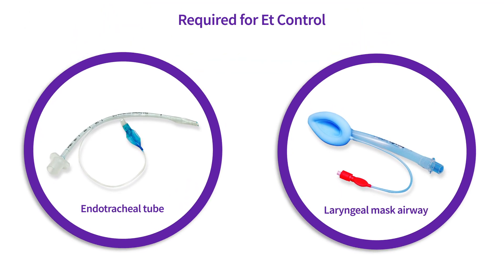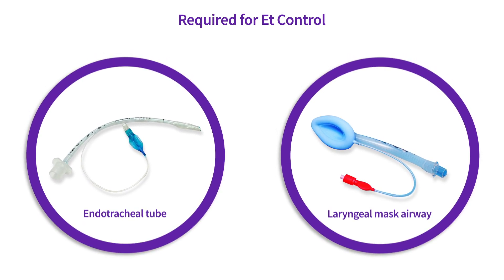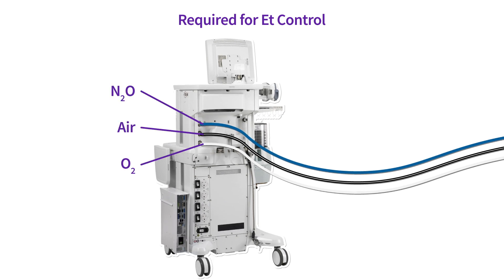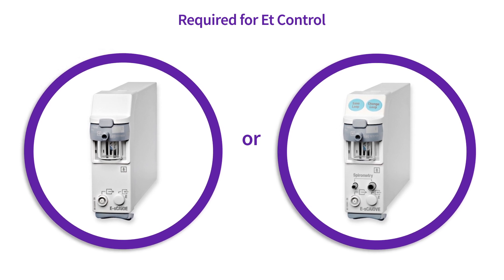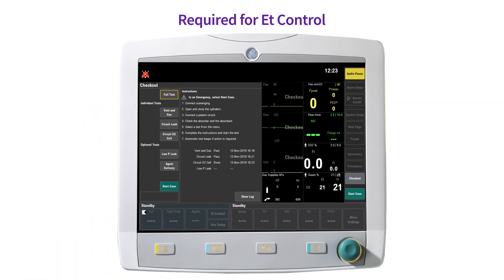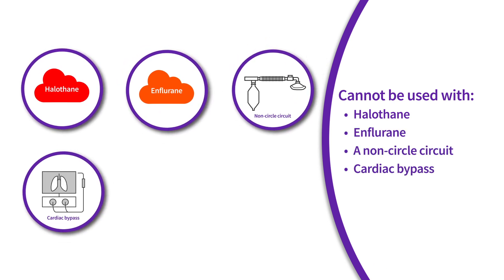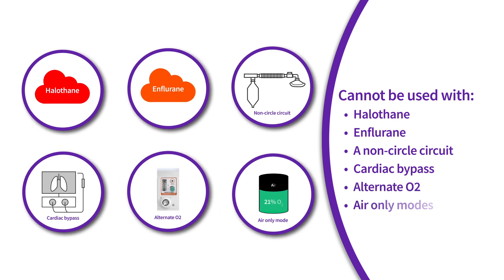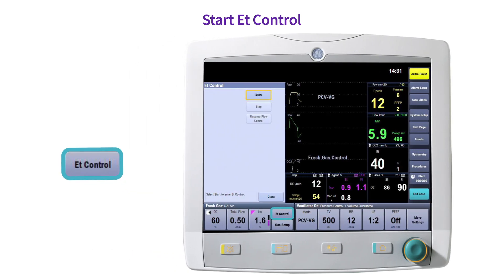Prior to initiating end-tidal control, a controlled airway such as an endotracheal tube or laryngeal mask airway should be used. The Aisys CS2 anesthesia delivery system should have a supply of oxygen and balance gas to enter end-tidal control mode. A CARESCAPE airway module with end-tidal control capabilities should be installed and warmed up. A full test checkout should be completed prior to use. It is important to note that end-tidal control cannot be used with halothane, enflurane, a non-circle circuit, cardiac bypass, alternate O2, or air-only modes.